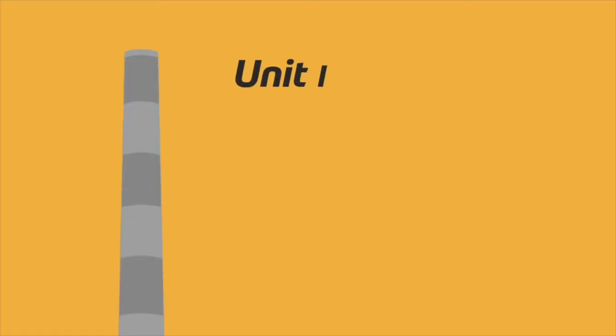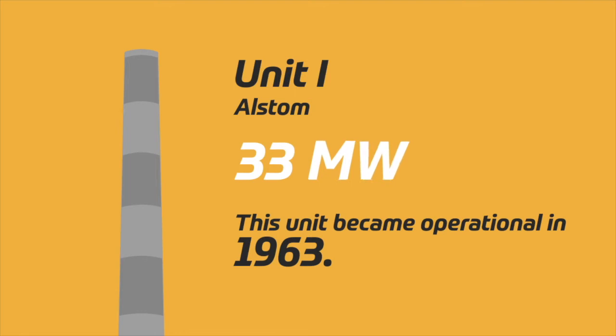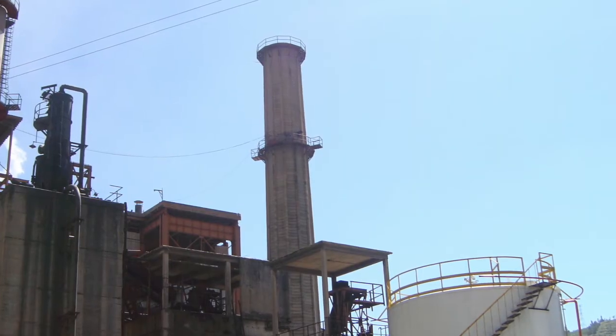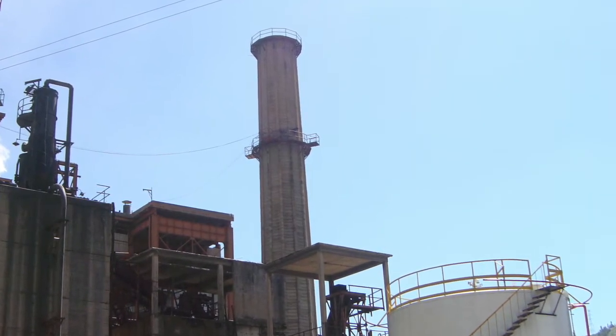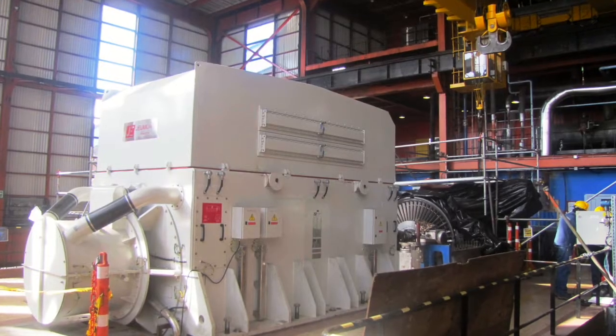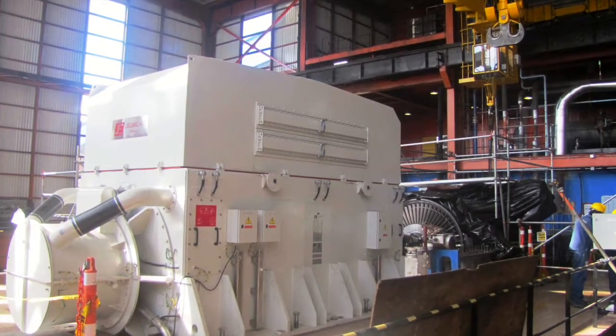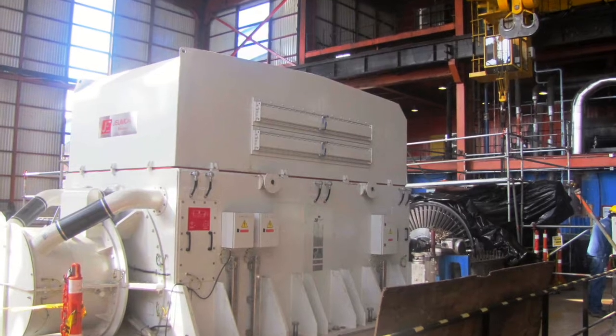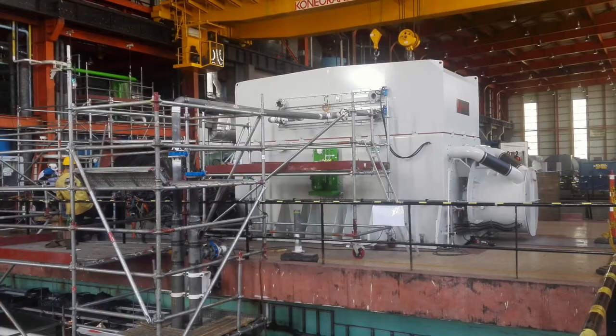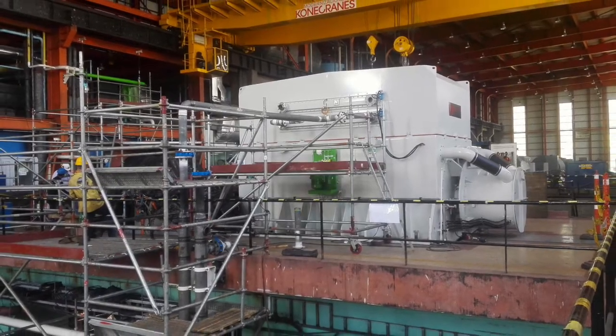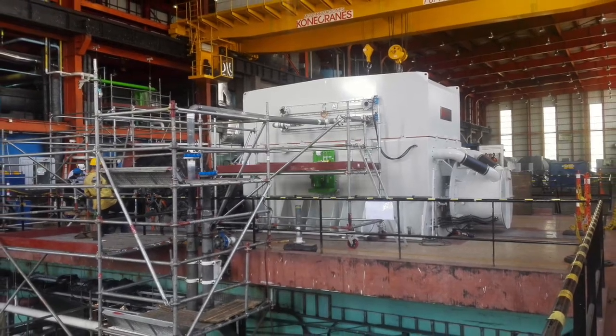Unit 1 is French technology, made by the firm Alstom. Its current capacity is 33 megawatts, and its boiler is a Stein et Roubaix. The unit became operational in 1963. This unit is currently undergoing a retrofit, and its turbine rotor is due to complete commissioning by the end of November 2016.